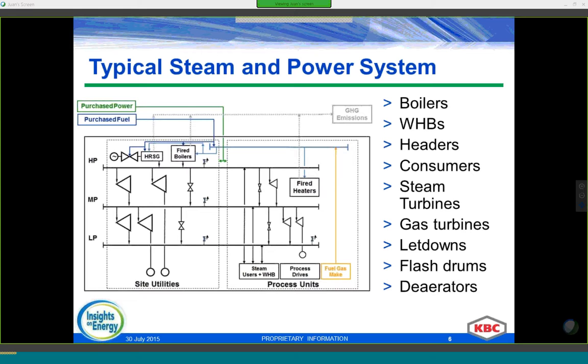The headers — typically site headers for HP, MP, and LP (high pressure, medium pressure, low pressure) — and also local headers for process units if they differ significantly from the site headers in terms of pressure. Steam consumers for heating steam, such as reboilers and tracing steam used on columns. Steam turbines — which could be turbine generators with multiple stages for power generation, back-pressure turbines, condensing turbines, equipment used to drive pumps and compressors — and also flash drums, deaerators, letdown valves, and the condensate recovery system.